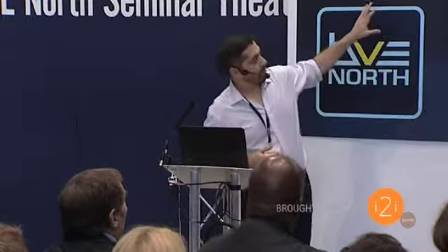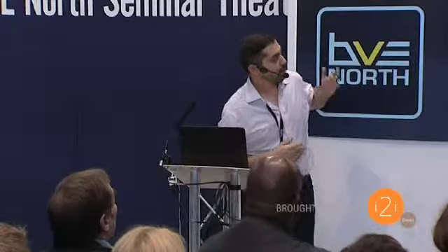This first shot is a rather ambiguous shot, really, of the strengthened floor under the machine room. There are 61 racks in the machine room, so it's pretty massive. It's so large and so heavy that we had to put these steel structures under the floors to distribute the weight. Otherwise, we'd have fallen through to the third floor, and I doubt the guys in Salford University would have appreciated that.